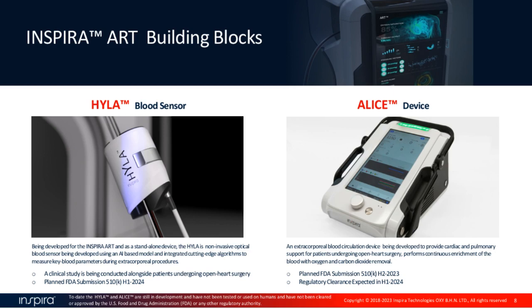But we can also take the sensor and connect it to the artificial lung, whether it's the ART or an ECMO machine or a machine that's used for open heart surgery. And we can actually monitor what's happening within the machine. In other words, if the blood coming out of the machine has any issues. It's designed to identify if there will be problems, let's say, with clotting or fatigue in the oxygenator. And why is that important? Because a lot of the time in these medical conditions, there's often either a problem with the patient or a problem with the equipment, and both of them have a huge impact on a patient and cause deterioration. And nobody knows about it.